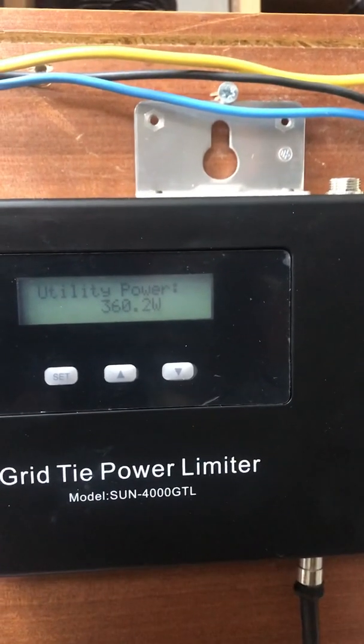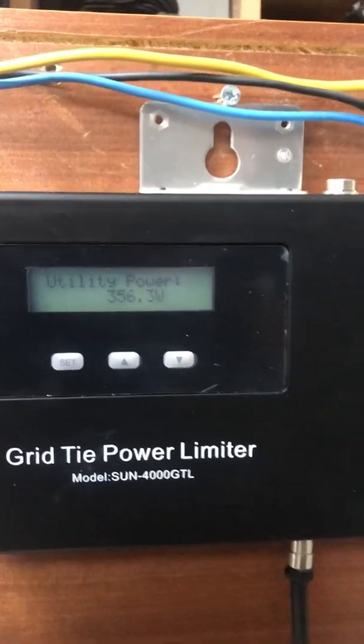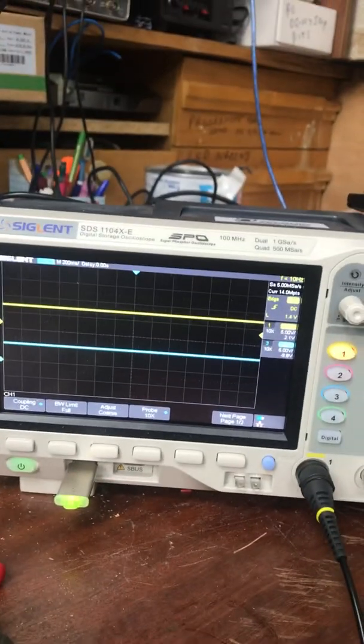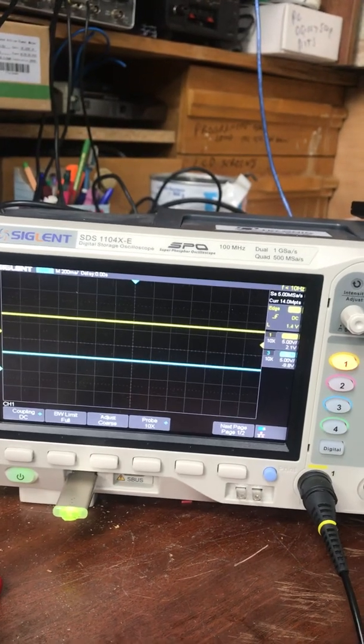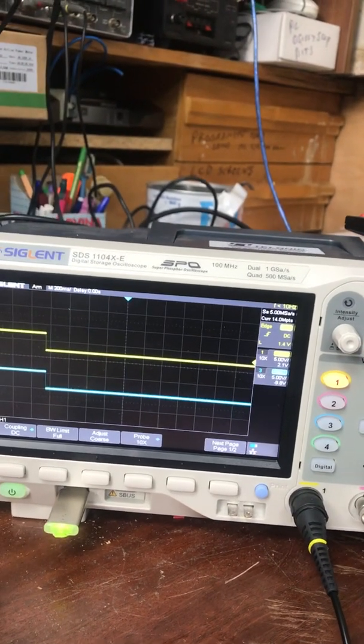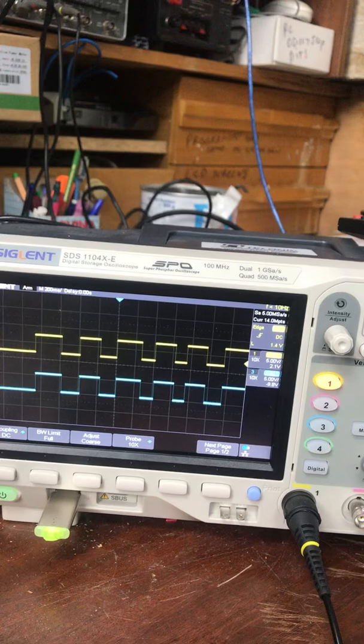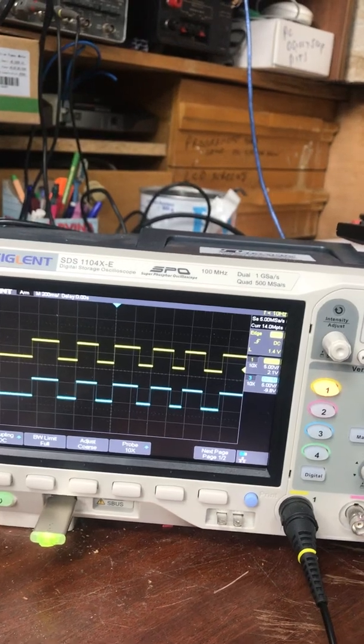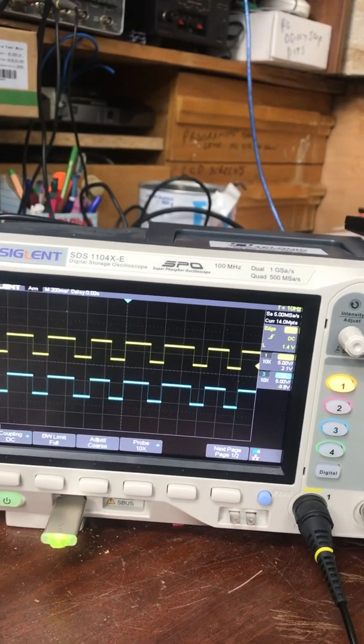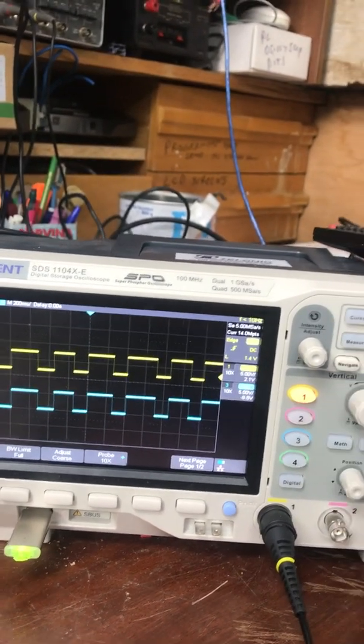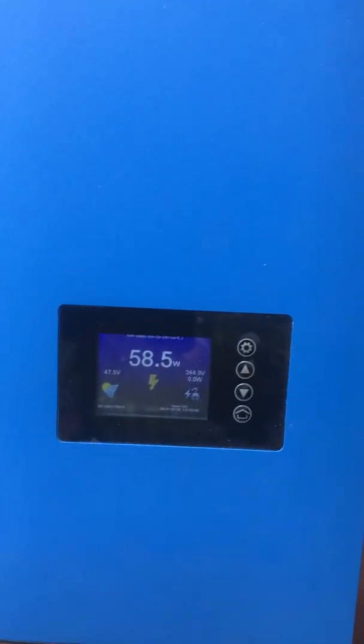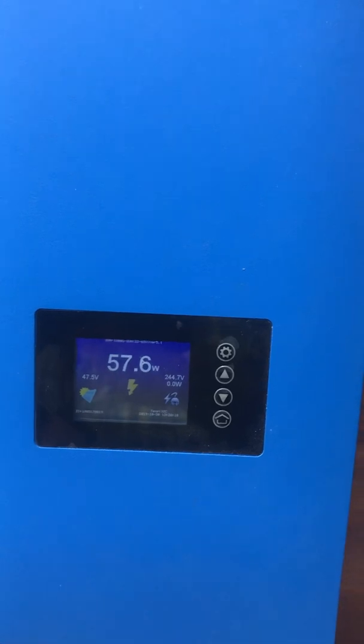Now if I turn the load off, I'll take it back to the scope, and then I'll turn it off and you'll see what will happen with the signal. In a moment, there we go—she's gone back the other way. And then we're back to our modulating signal. You can see slight differences in lengths as it sorts itself out, and we come back to our controller here. We're back to our 58.